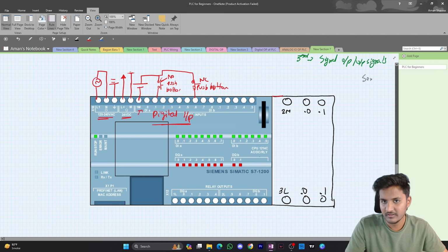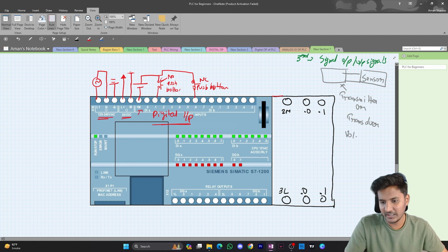So there will be a sensor here. The sensor will have some signals. It will go to a transmitter, or you can say transducer, which will give either a voltage type or a current type output. So voltage may vary from 0 to 10 volt and current output will be 4 to 20 milliampere. So assume we have a current type, so it will have a positive and negative. So as we are using a sinking type, it will be a DC output. So we'll connect our negative terminal to here, negative, and positive to here.